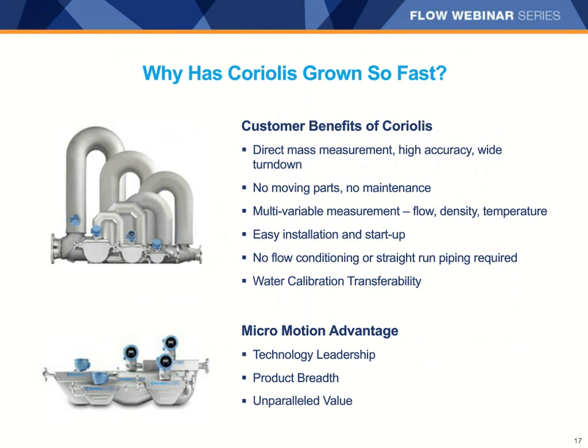Now let's talk about some of the reasons why the use of Coriolis technology has been growing. First, its direct mass measurement, as previously discussed, as well as its high accuracy for both mass flow and density: plus or minus 0.05% of mass flow rate, and plus or minus 0.002 grams per cc on density. Coriolis meters also have very large accuracy turndown, no moving parts, therefore no maintenance, easy installation and startup, multivariable measurement, meaning flow, density and temperature out of one device, no flow conditioning or straight run piping is required, and last, the water calibration transfers to other fluids, which keeps calibration simple and its cost low.